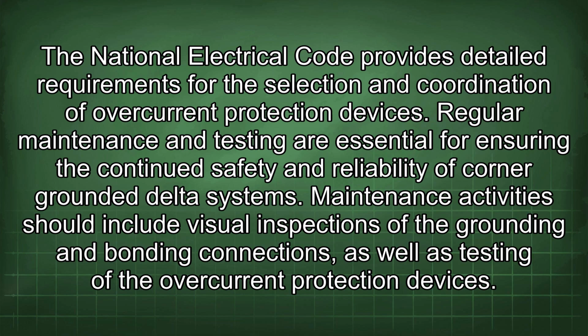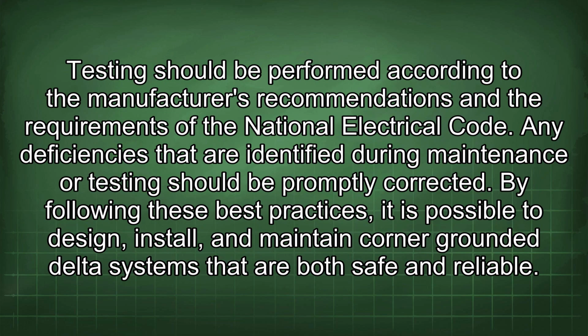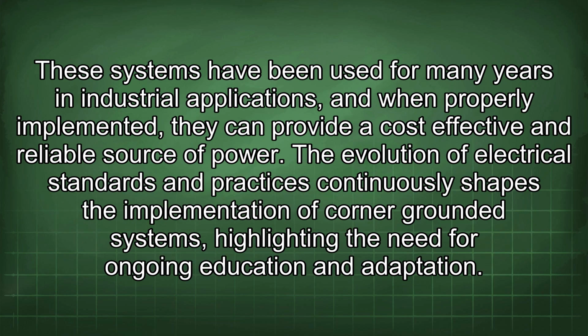Regular maintenance and testing are essential for ensuring the continued safety and reliability of corner-grounded delta systems. Maintenance activities should include visual inspections of the grounding and bonding connections, as well as testing of the overcurrent protection devices. Testing should be performed according to the manufacturer's recommendations and the requirements of the National Electrical Code. Any deficiencies that are identified during maintenance or testing should be promptly corrected. By following these best practices, it is possible to design, install, and maintain corner-grounded delta systems that are both safe and reliable. These systems have been used for many years in industrial applications, and when properly implemented, they can provide a cost-effective and reliable source of power.